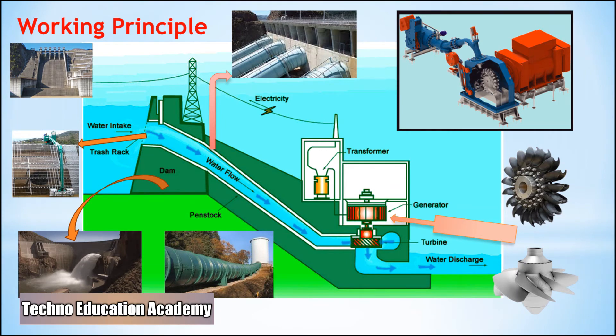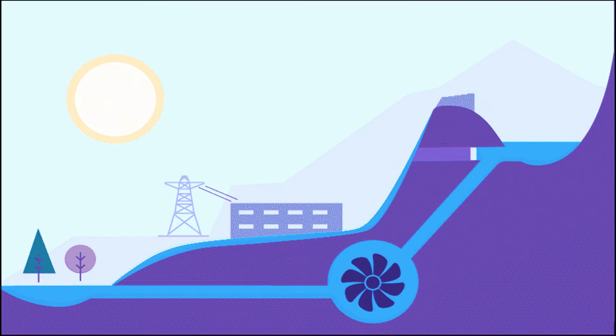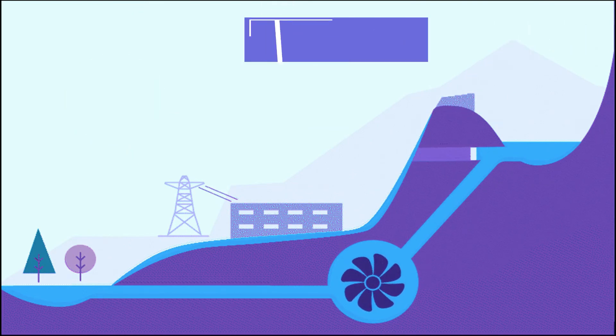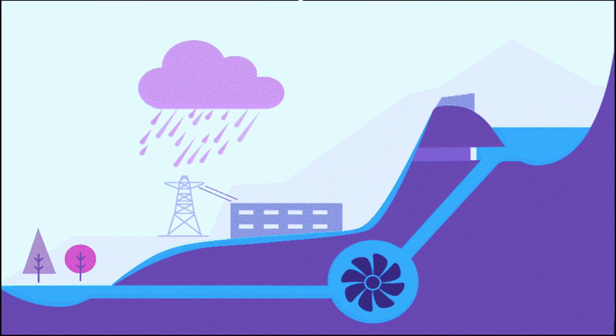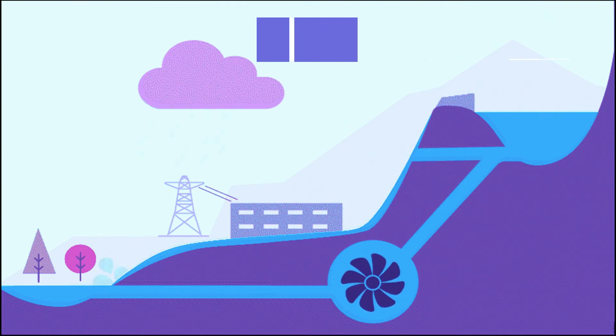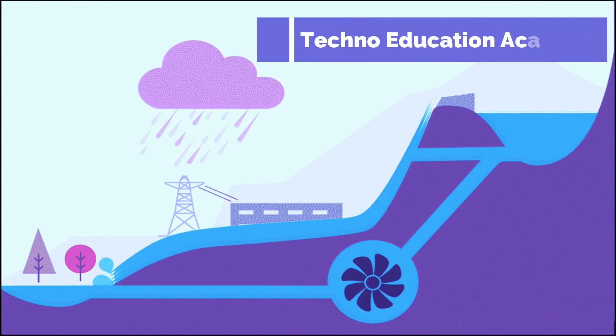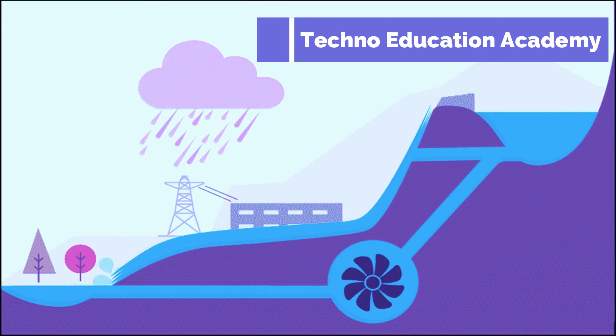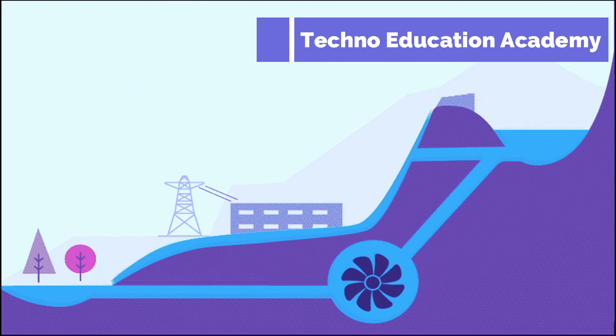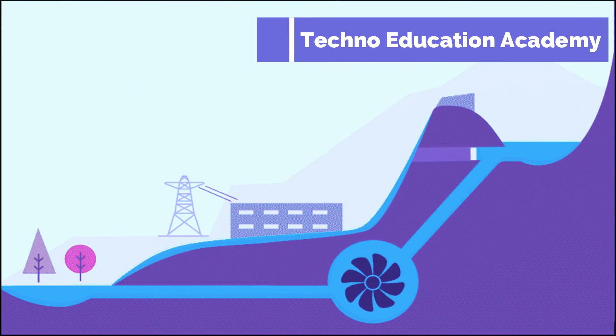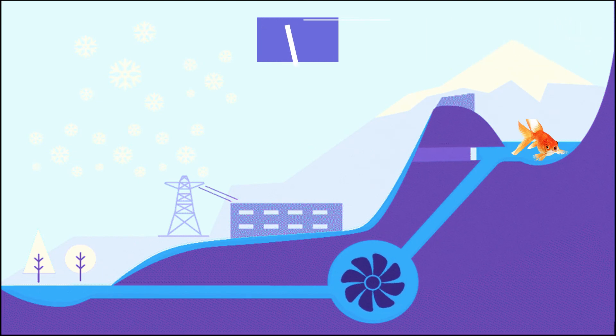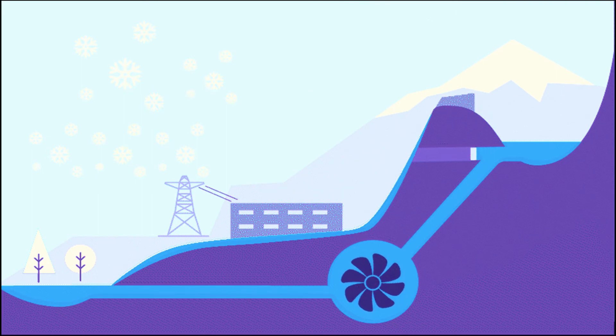The second type of hydroelectricity production is the run-of-river hydro. A run-of-river plant produces energy from the available flow and the natural elevation drop of a river. It is suitable for rivers that have at least a minimum flow all year around. Such a plant can be with or without pondage. A run-of-river plant without pondage has no control over river flow and is subject to seasonal river flows, making it an intermittent energy source that usually supplies peak load during floods. A run-of-river plant with pondage may supply base load or peak load power — at times of high water flow it may be base-loaded, and during dry seasons it may be peak-loaded.